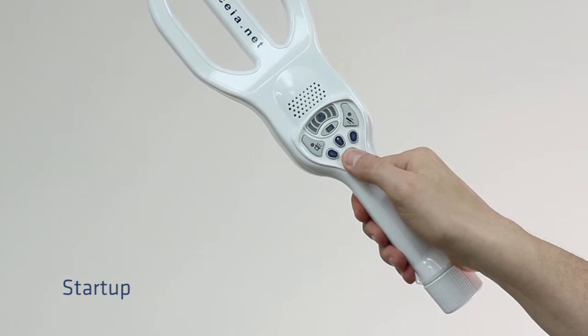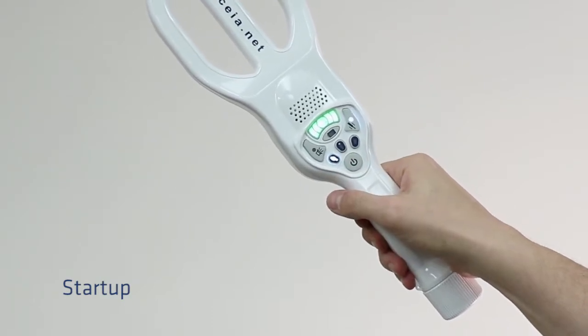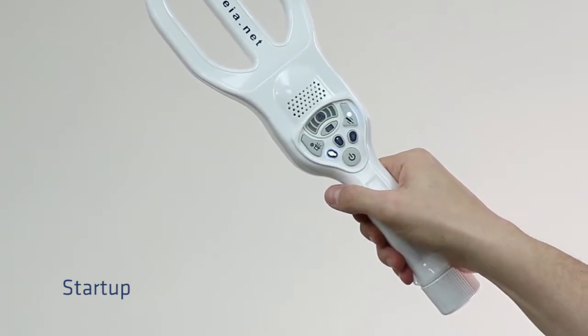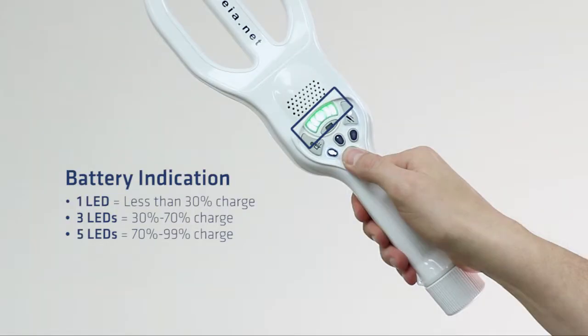Press the power reset button. The optical alarm indicator will briefly flash red in the center, followed by a battery level indication in green. The detector is ready for use when all audible and visual alarm indications stop. This is approximately 2 seconds after pressing the on-off button. Note, during startup, all 5 lights in the optical alarm indicator indicate the battery is charged over 70%. 3 lights indicate a 30 to 70% charge, and 1 green light means the battery is less than 30% charged.